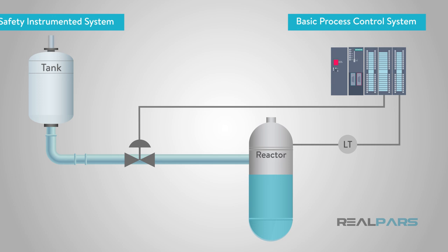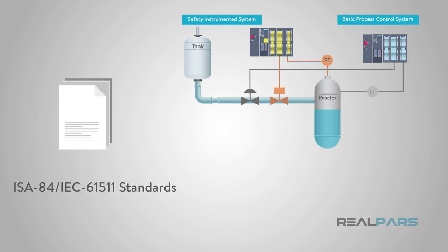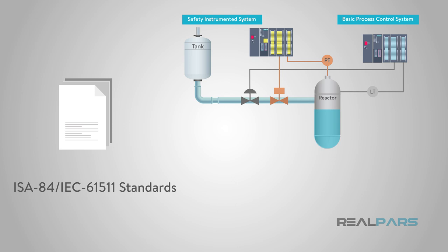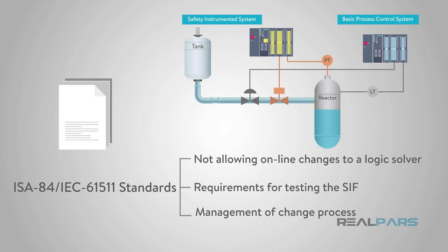When designing a safety instrumented system, the ISA 84 / IEC 61511 standards prescribe a methodology for developing and documenting the system. Certain design principles should be followed, such as not allowing online changes to a logic solver, requirements for testing the SIF, and a management of change process for making any changes to the system once the design has been approved.